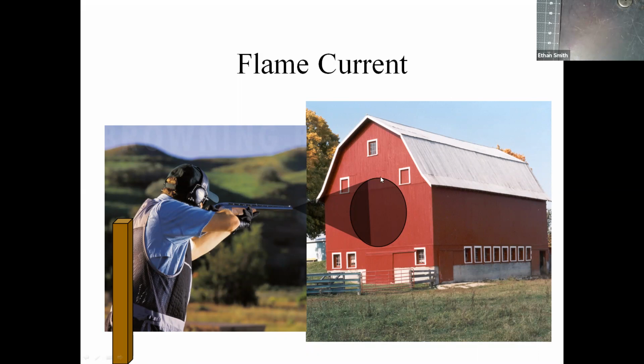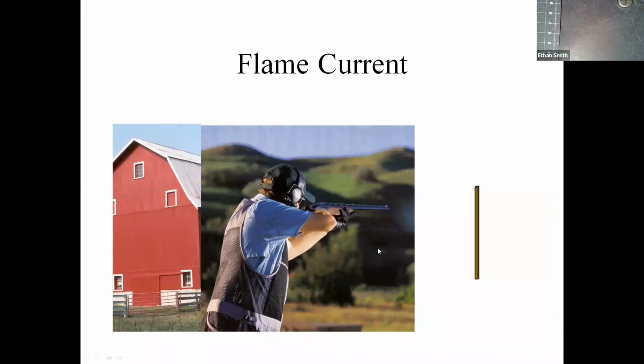Okay. Flames are actually electrically conductive to a small degree, but they're only electrically conductive where the flame is actually burning. Okay, so the flame out of a burner actually only has an active flame on the exterior part of the flame. And so what we're doing when we do flame current is we actually send a high voltage signal, sometimes up to 120 volts in residential stuff, up through that flame sensor, or this is our post. So if we have this guy with a shotgun and we have him shoot at that post, where is that post going to receive pellets?